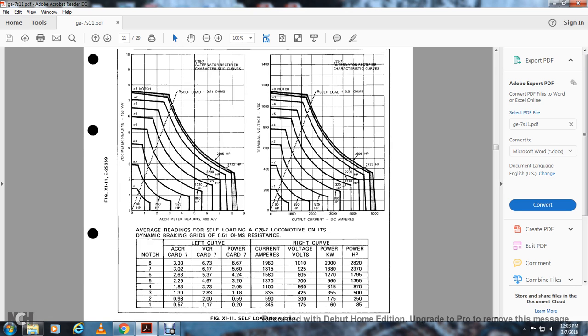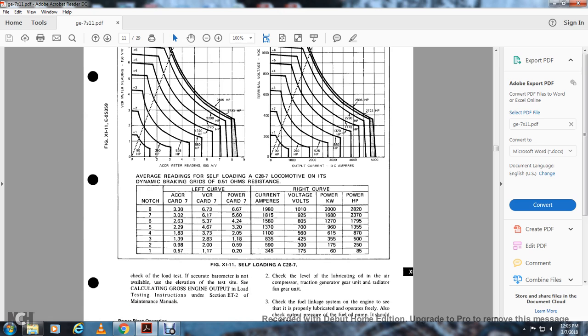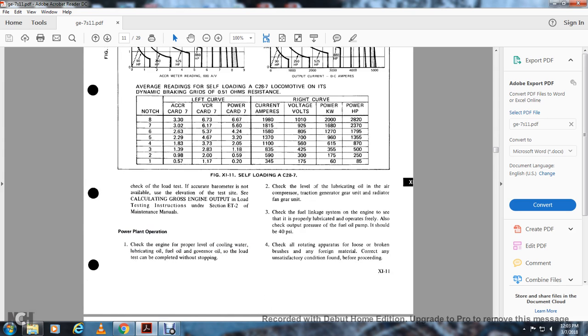Output current, DC amperes 1000, 2000, 3000, 4000, 5000. Average reading for the self-loading C28-7 locomotive, with the dynamic braking grids at 0.51 ohms resistance. Notch 8 through 1, ACCR card 7, VCR card 7, power card 7, left curve, right curve, current amperes, voltage volts, power kilowatts, power horsepower.